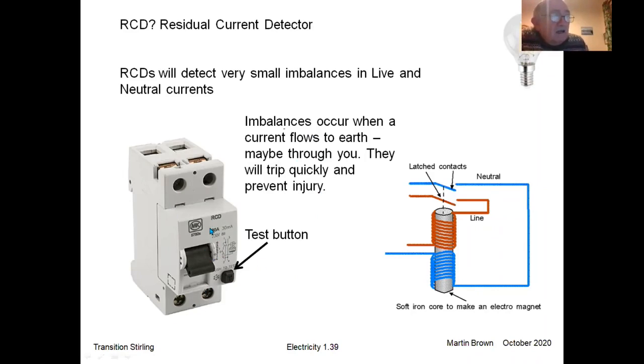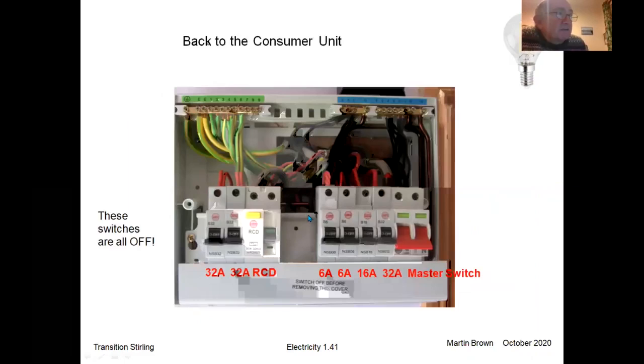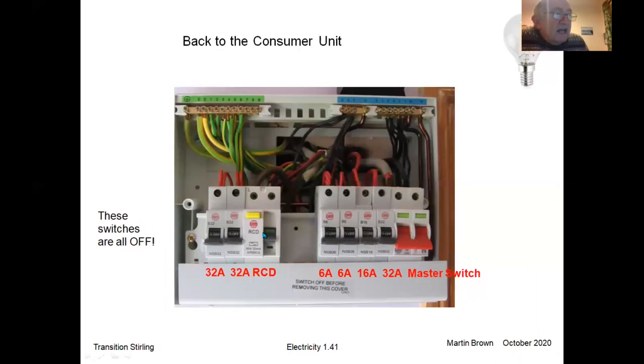So RCDs have been around for 40, 50 years, something like that, and now they're just part of what's in your consumer unit. What that means is, when we go back to our consumer unit and we're thinking about protection and the faults, it's quite possible that the RCD will trip open as well as or instead of one of the MCBs. So that's another item to look at. And in my experience, the RCD often trips if you get something like a sudden overload, like an old-fashioned bulb blowing. It always seems to open these up. We'll talk briefly about how to troubleshoot that in a minute.